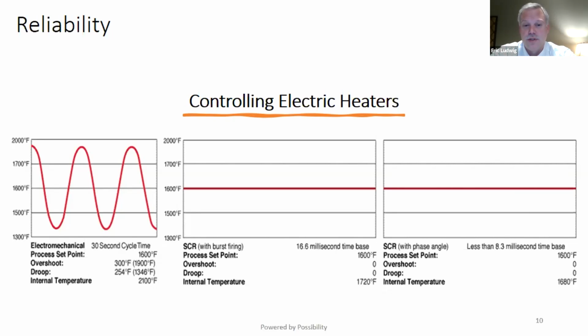So in the middle graph, you see what's called an SCR with burst firing. Burst fire is something that switches on and off very, very quickly. You see the time base there at 16.6 milliseconds. That particular burst fire mode helps even out the outlet temperature and also provides a much cooler heater element temperature. You see that 1720. And then finally, on the right-hand side, you see a phase angle controlled SCR. This is where every sinusoidal signal that's going to the particular branch circuit gets cut, if you will, or controlled at a very specific interval to provide a very specific amount of power within that single sinusoidal signal. So that produces your lowest internal temperature at 1680 degrees Fahrenheit. And again, a nice smooth curve. So what does that mean to the overall life?